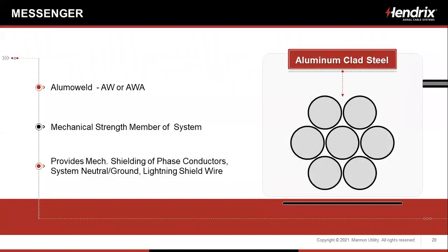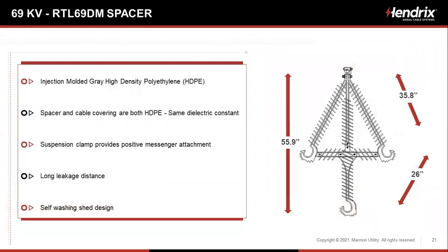For the messenger, we're going to use Alumoweld aluminum, which basically has a heart of galvanized steel with a 10% cladding or coating of pure aluminum. If we need more ampacity, we're going to take out some of those Alumoweld strands and replace them with pure aluminum strands. And that's what we call AWA, Alumoweld aluminum. That's going to have several functions. It's going to be the mechanical strength member. It's going to hold everything up in the air. It's also going to act as a system neutral. It's going to act as a lightning shield for that transmission line. And it's also going to keep things that fall on that system from above from damaging those phase conductors. And we'll see a few photos on that as well.